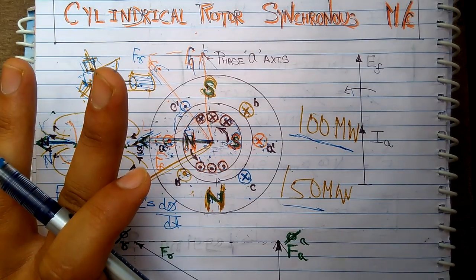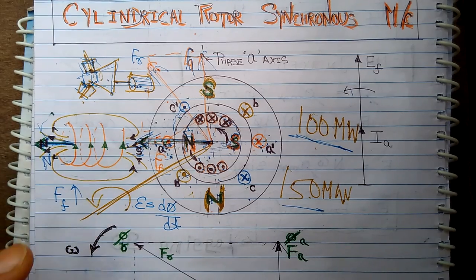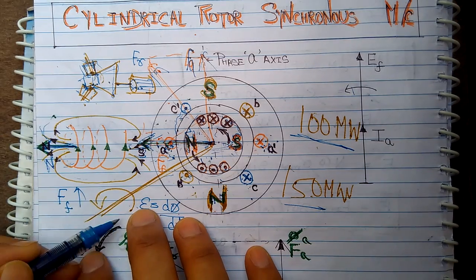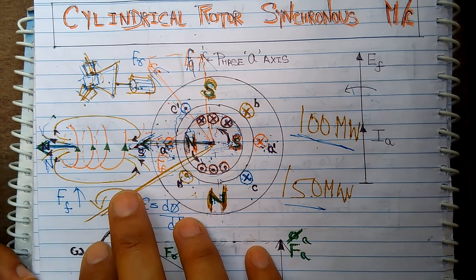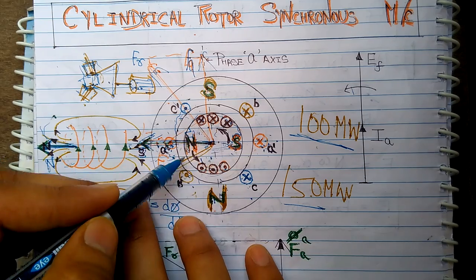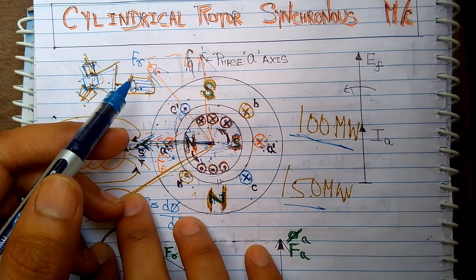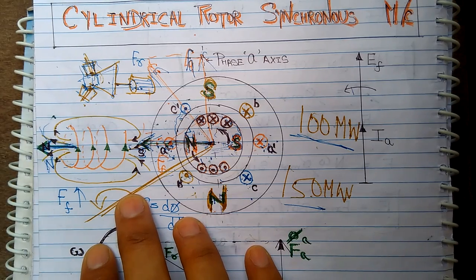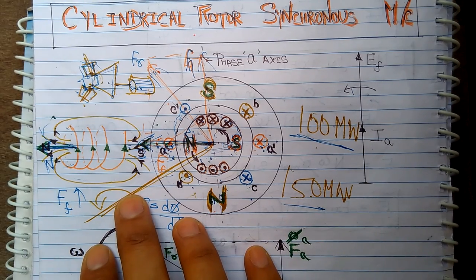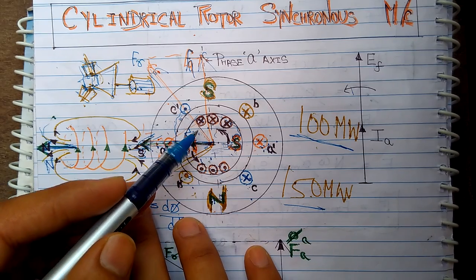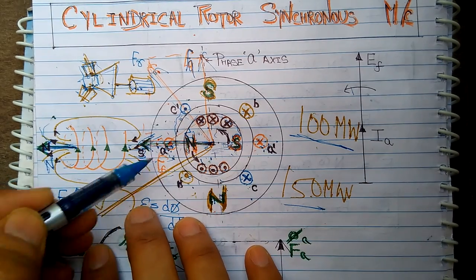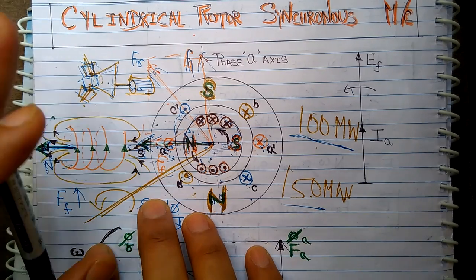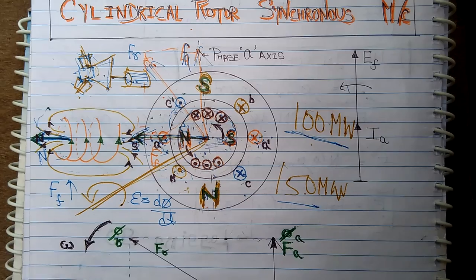Now I have two torques running on this rotor. One is the anti-clockwise direction torque produced by mechanical means — by the turbine and steam. The second is electromagnetic torque produced in the clockwise direction due to Lenz's law. If I want my rotor to rotate at constant speed, these two torques must be balanced. If the two torques are balanced, the rotor rotates at constant speed because there will be neither acceleration nor deceleration.